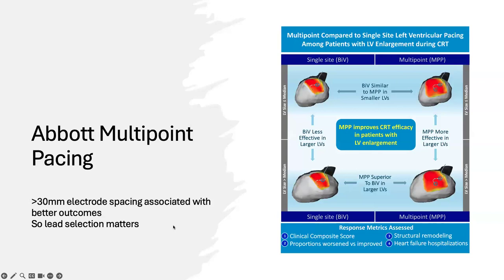Battery life considerations do have to be taken into account, especially if you're using a reprocessed device or if it's a patient where this is an economically impactful device that they bought and they're worried about buying another one down the road.